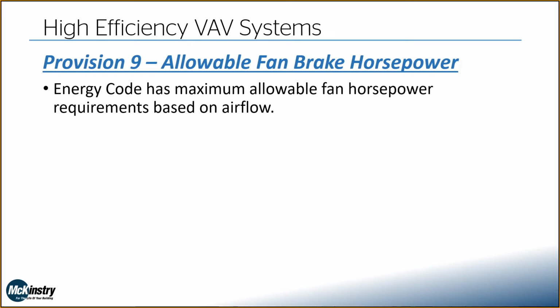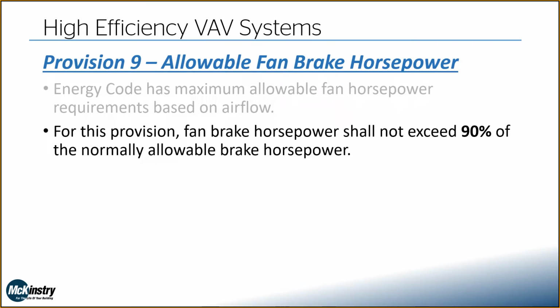Allowable fan brake horsepower. The energy code typically has a maximum allowable fan horsepower based on the airflow you're providing. So if your system is providing 10,000 CFM of air, there's a maximum horsepower allowed to deliver that amount of air. But for high efficiency VAV, you can't exceed 90% of what's normally allowed. So if you're normally allowed a 20 horsepower motor, now you're not supposed to exceed 18.